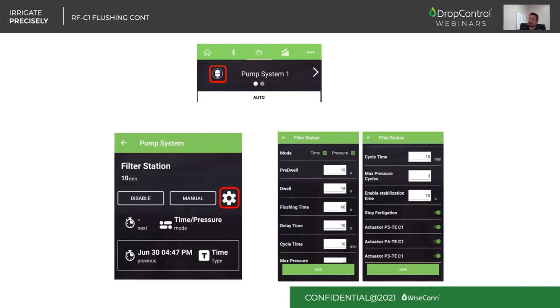Moving from the web browser version into the mobile app, the mobile app is also capable of displaying, through this icon that is representing the flushing, a second view that will allow you to have interaction with the unit. So you're going to be able to also disable any flushing features. You can trigger a manual flushing, so you don't need to be next to the site. You could be wherever and activate this remotely as soon as you have cellular connectivity in your phone. And obviously the RFC1 controller also has cellular connectivity in the field. You can also modify the different settings, and you can see when was the previous cycle and how it got triggered. In this case, it has the date and time, and that it got triggered by time or frequency. And on the settings, the same parameters or operation modes that you're capable of controlling on the web browser, you can do through the mobile app.